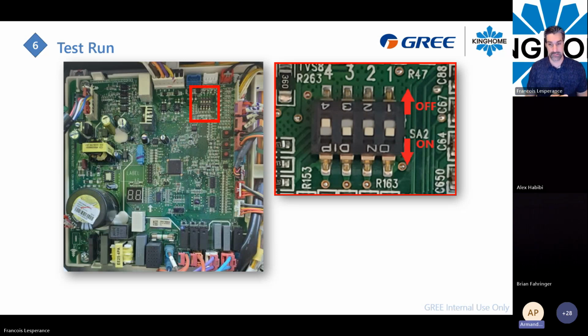Okay. So whenever we are going to change the 3-ton unit from 3 to 3.5 by turning the dip switch on, will the coil adjust accordingly, or do we have to use the 3-ton coil? We have the 3-ton coil inside, and outside we have a 3-ton unit, and we are increasing the capacity from 3 to 3.5 ton outside. So it can accommodate inside. No, you don't have to do anything inside.